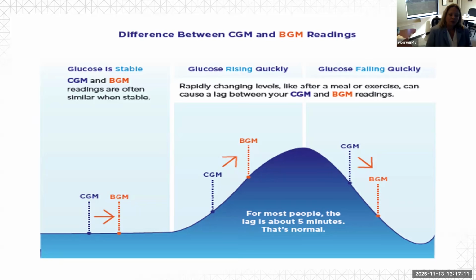So if you look at this graph here, think of a train. If I have an engine and a caboose, the engine is my blood sugar reading in the red. My caboose is the continuous glucose monitor. If my tracks are flat, I'm not going uphill, they're going to be pretty close together. The numbers are going to be fairly close. But let's just say I just got done eating a big meal with a lot of carbs. My blood sugar, which is going to be my finger stick, is going to be much higher than my sensor reading. The reason is that the sensor is monitoring blood sugar in the interstitial fluid that's around the cells. So when you eat food, it goes into your bloodstream first, and then it goes into the interstitial fluid. So there's a lag time between the blood testing and the sensor testing, about 5 minutes, and sometimes even 15 minutes. So you just got to make sure that people are aware that if they're rapidly increasing or rapidly decreasing in blood sugars, there's going to be a bigger span between the two readings of a sensor and a blood sugar meter.